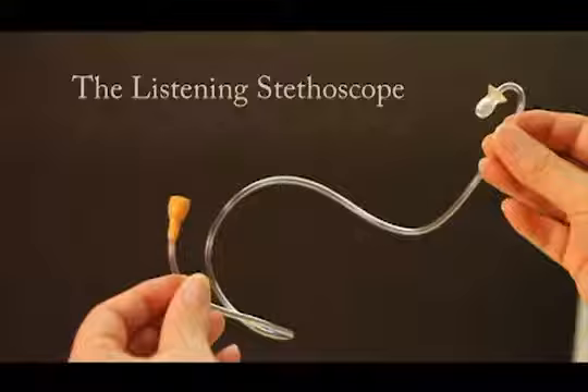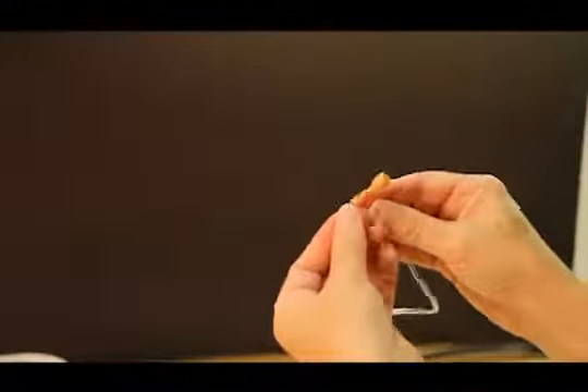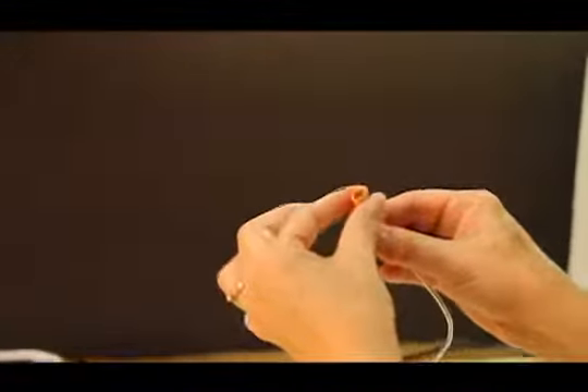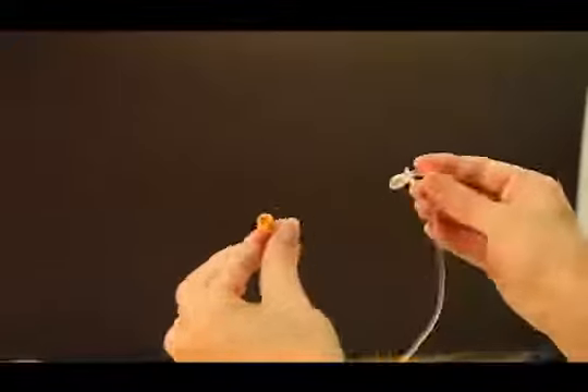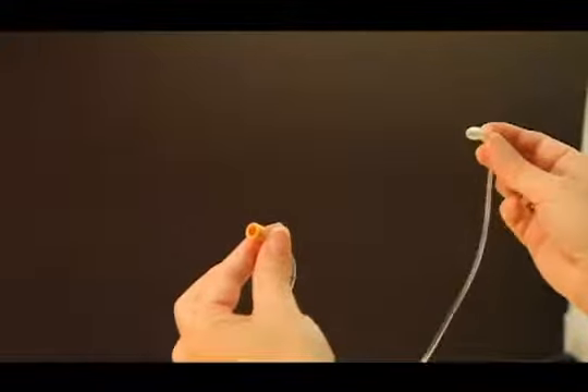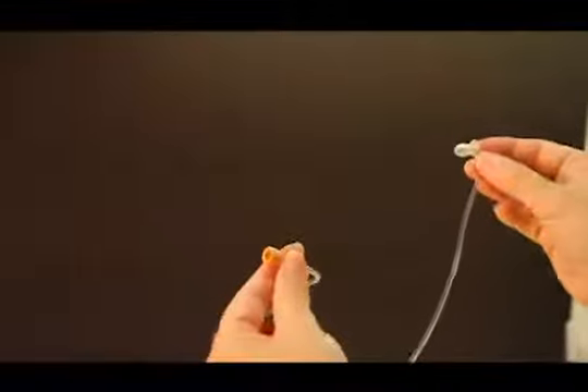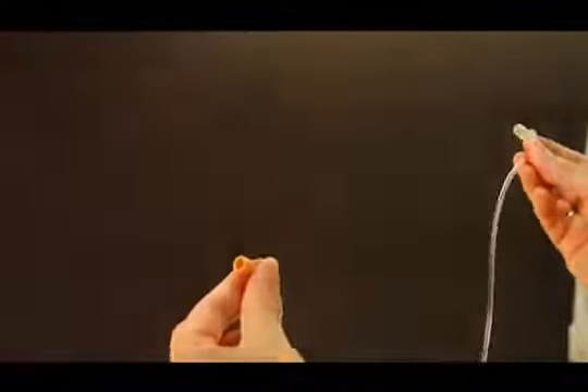Once you have checked the physical condition, then you can listen to the hearing aids using the listening stethoscope. Place the bulb-shaped end into your ear canal, and the flared or bell-shaped end connects to the ear mold. It needs to fit snugly around the ear mold because if amplified sound leaks out, you will hear feedback and it will be hard to tell if the hearing aid is working properly. Feedback is a whistling sound, and it happens when amplified sound is picked up by the hearing aid microphone.